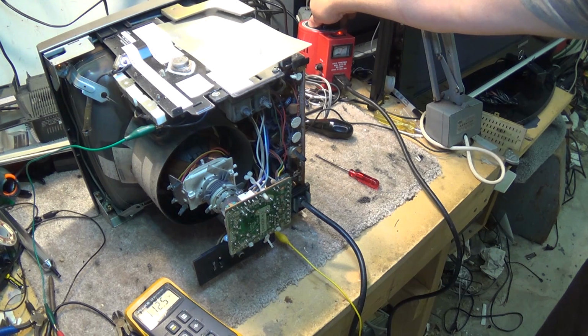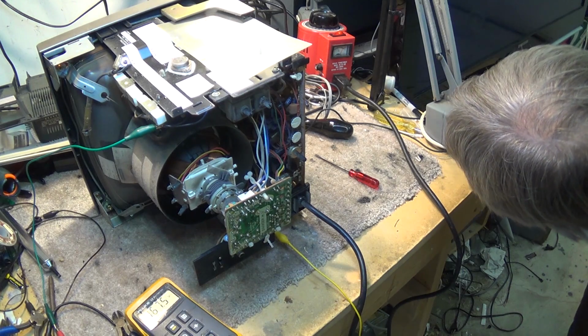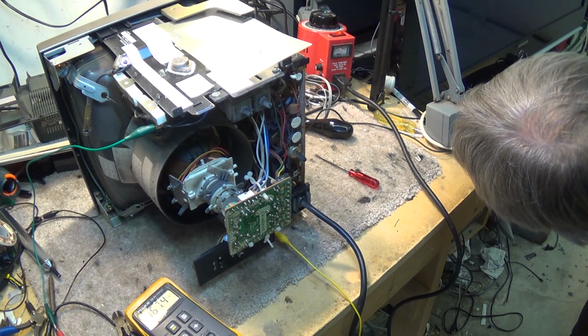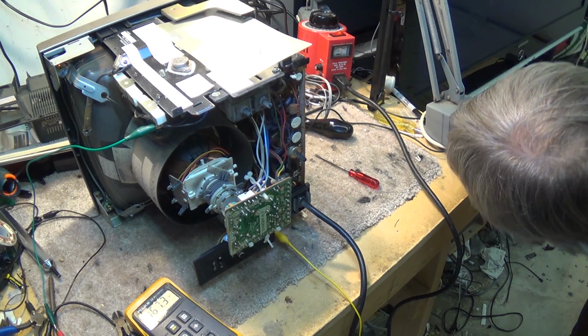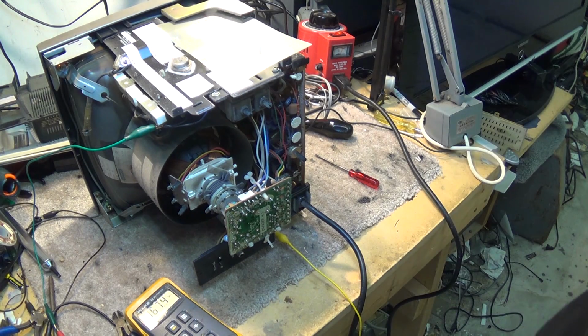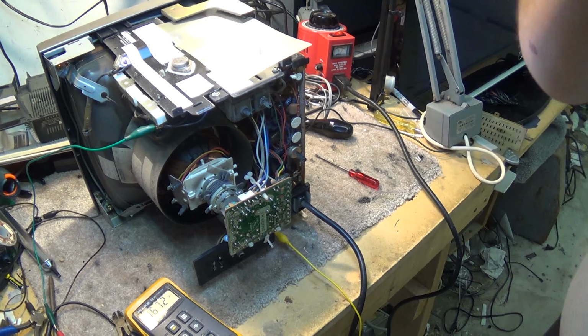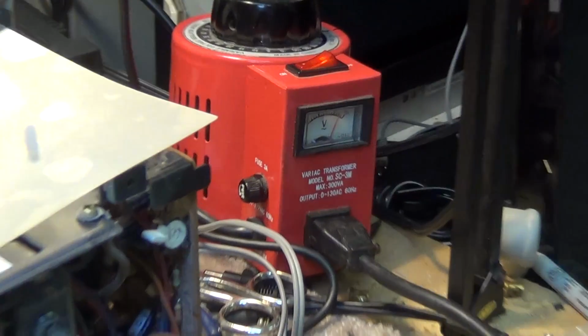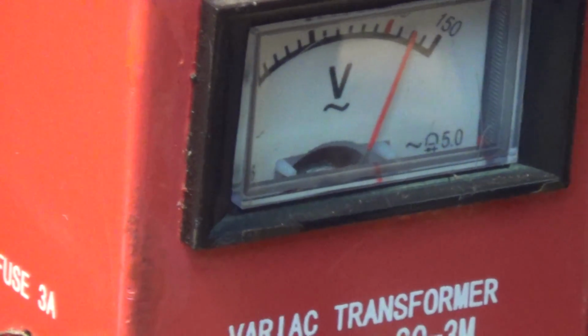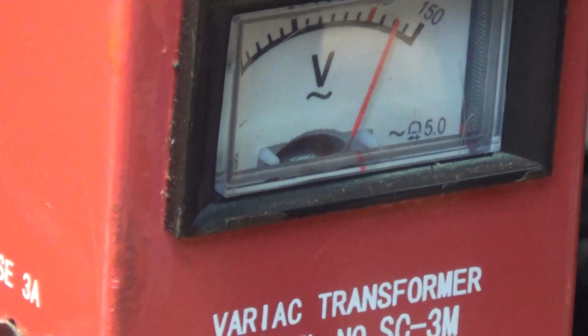So I'm increasing the voltage now. Still holding at 100. Okay, it shut down now. It's at about 130 - 110, 100, yeah, about 130 volts. If we look at the variac here, it's got a voltmeter on it. As you can see, 130 volts, that's where the set went into shutdown.